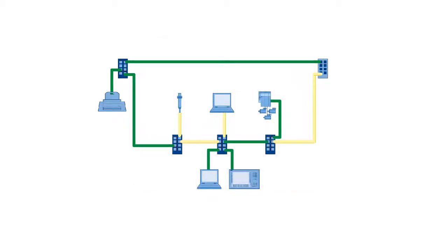The ring is logically disconnected at the position of the ring redundancy manager. The regular communication is routed around the redundancy manager as if the ring was really a straight line. Its endpoints are the two ring ports of the redundancy manager. One of the two ports is referred to as active, the other one as passive. In addition to normal data traffic, the redundancy manager sends special multicast telegrams to the network via the active ring port at 10 millisecond intervals.